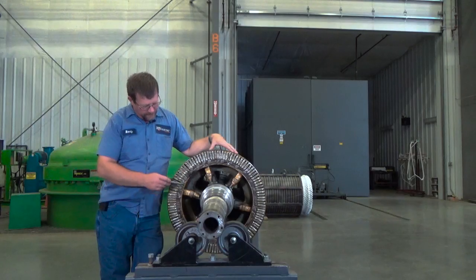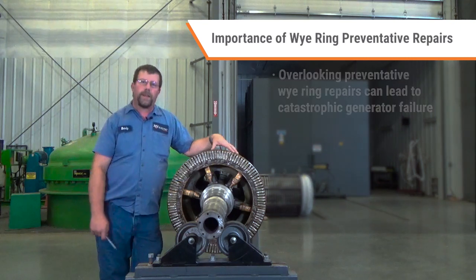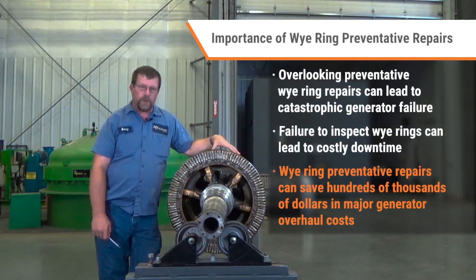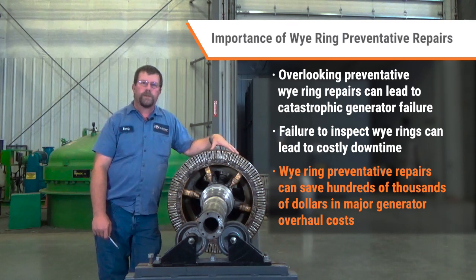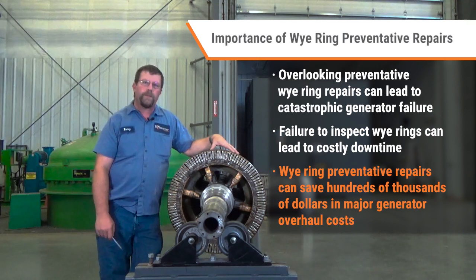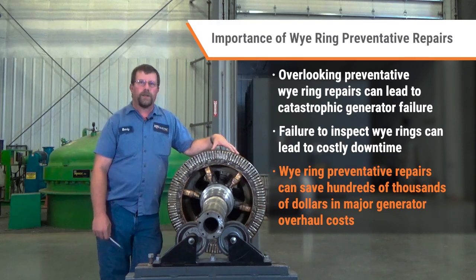What we like to do at H&N is find these cracks developing in this wye ring through borescope inspections, which we do up tower before the generator has a catastrophic failure. Then we actually send our crews up and we replace this wye ring while the generator is still in the tower.